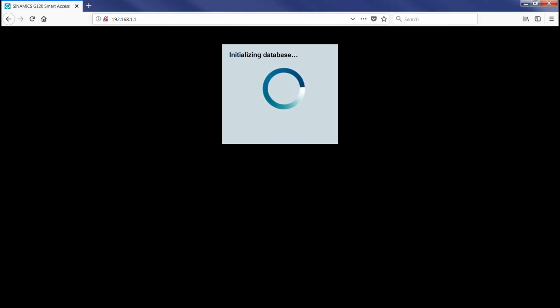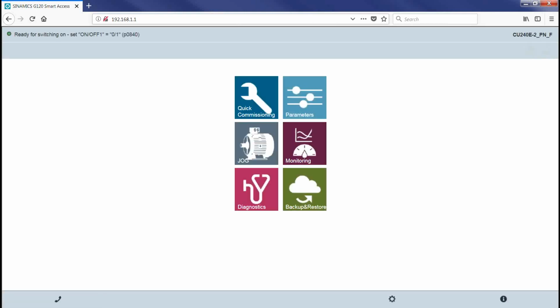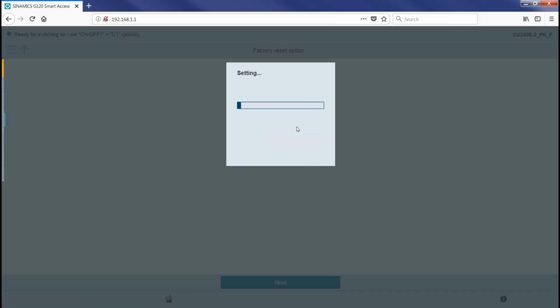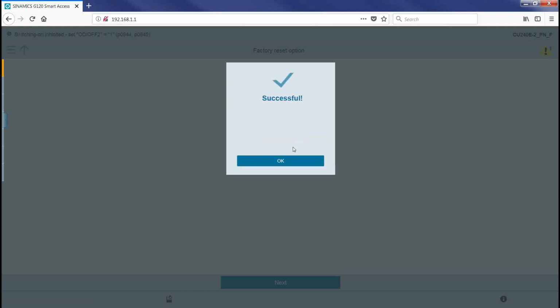So this one takes a little longer to initialize. You'll see this pop up. See top left again, ready for switch on, status of the drive. Top left shows you what model of drive. I've actually got a fail-safe drive I'm showing, but again, I can't do any of the fail-safe parameters or safety parameters through this. So we'll go through a quick commissioning real quick. I'm going to say reset the factory settings. Takes a little longer for the G120 to reset all. Okay, successful.